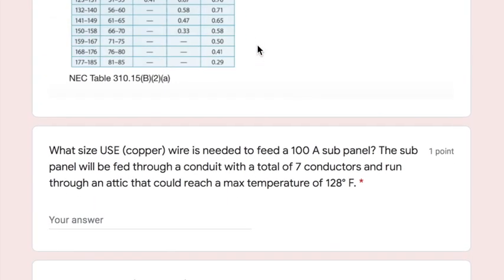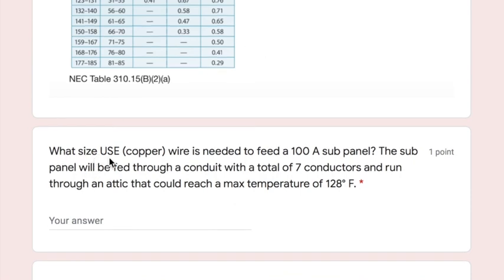In this case, because we're doing adjustment and correction, we have to take into account that we have more than three current carrying conductors, and we are also going to have an ambient temperature which is more than 30 degrees or 86 degrees Fahrenheit. Okay, so our first problem here says: what size U.S.E. copper wire is needed to feed a 100-amp subpanel? The subpanel will be fed through a conduit with a total of seven conductors and run through an attic that could reach a max temperature of 128 degrees Fahrenheit.